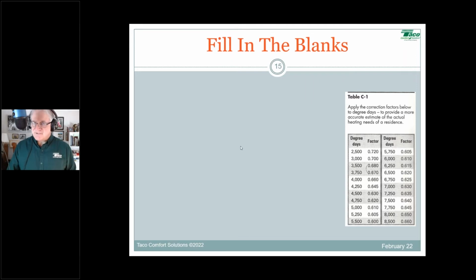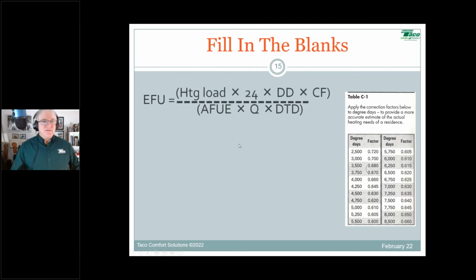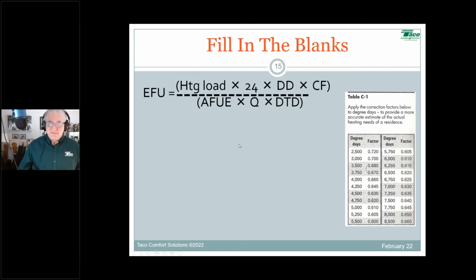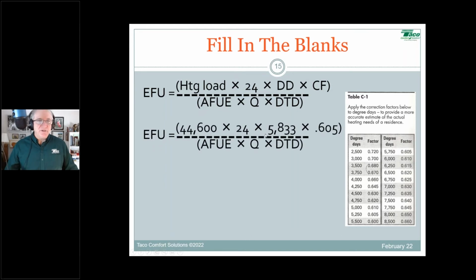So let's fill in the blanks, let's start doing some math here. So there's our formula, let's fill in what we know. We know the heating load, 44,600 BTUs, 24 hours in a day, that doesn't change, and 5,833 degree days.